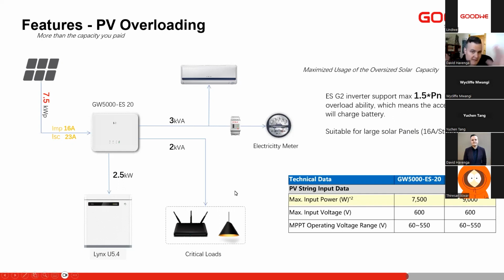And obviously, it depends. If your load is lower, it will use more to charge the batteries, up to a maximum of 5 kilowatts charging the batteries, and then the rest can go to the AC side. This gives us a lot of flexibility, especially in off-grid scenarios where you might need a larger PV system, but you don't necessarily need a larger inverter. And just to mention also the 6 kilowatt, we can put 9 kilowatts of PV.